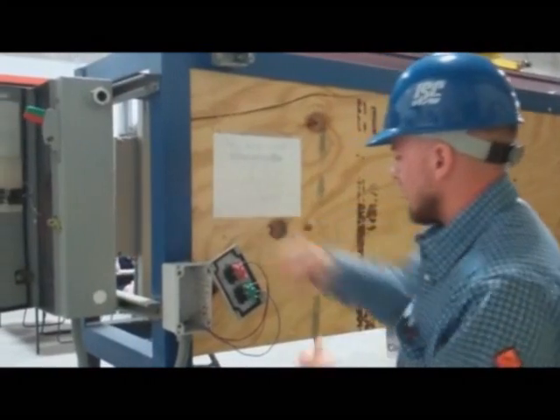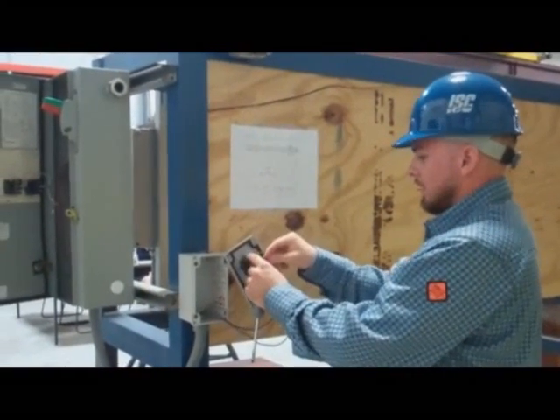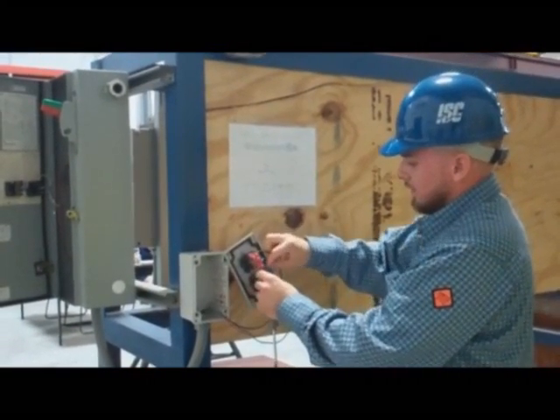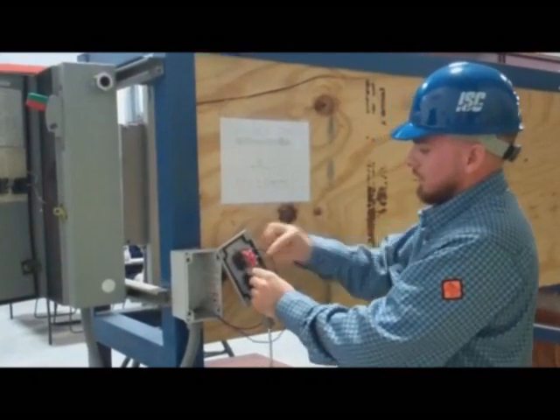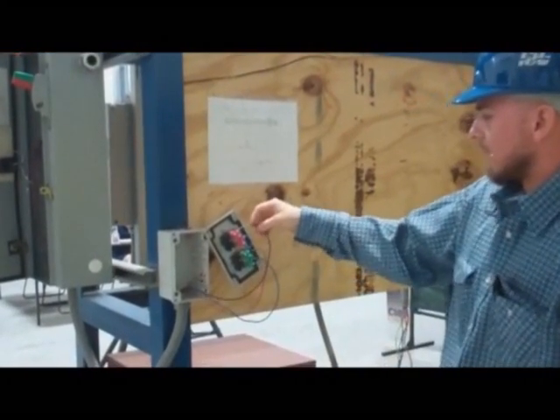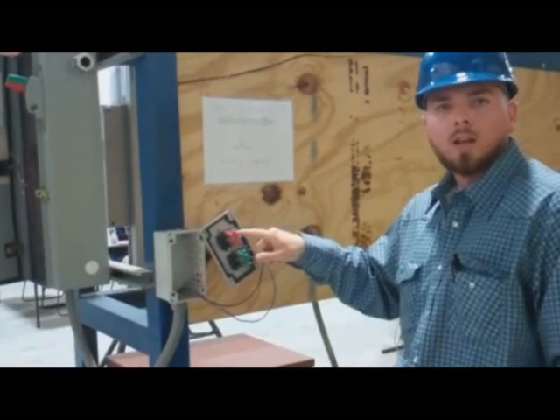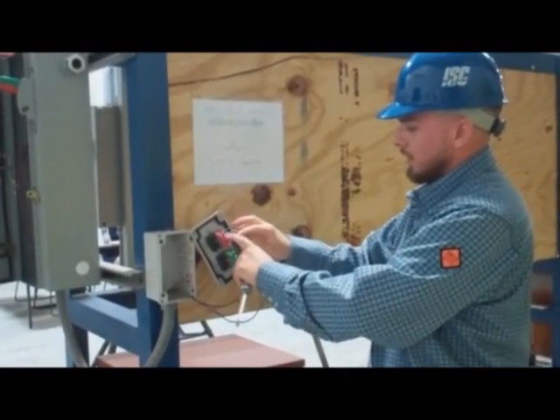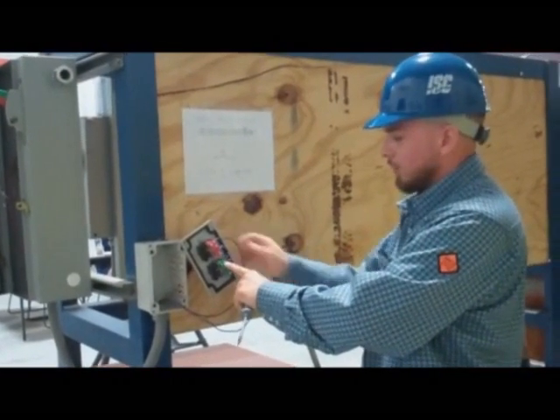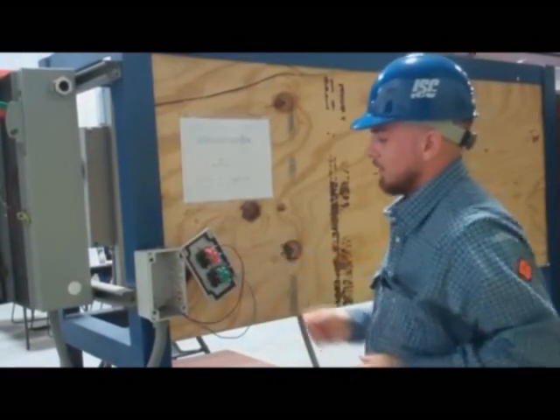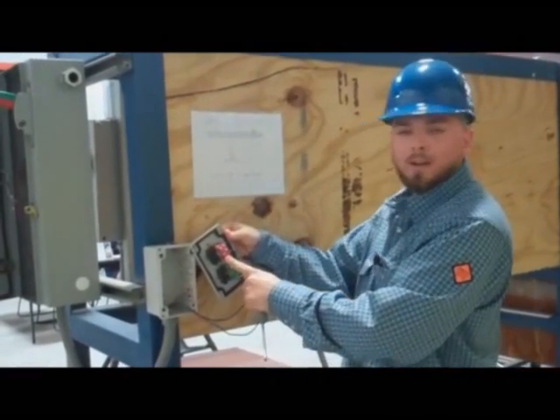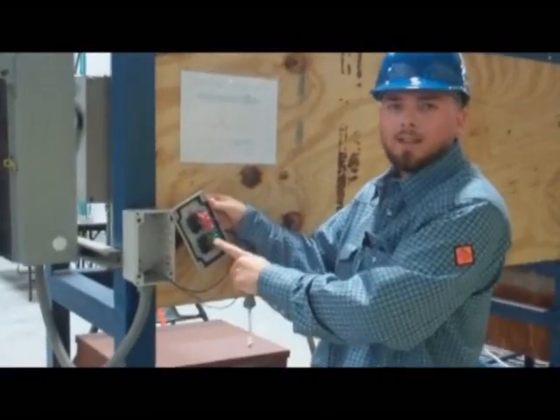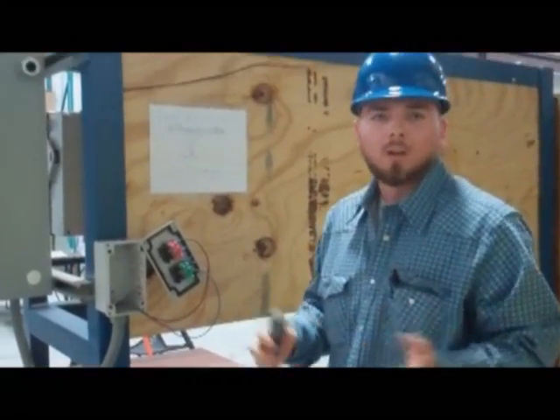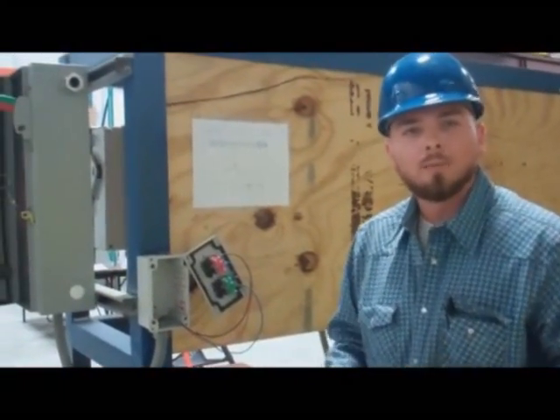And then you guys follow a jumper. What you have is you have your black wire coming out on your normally closed on the stop. It jumps over, because these normally closed contacts, it jumps to your normally open on your start. So when they stop that motor, you push that stop button, it opens up those contacts, and that kills the power to the motor. So they can stop and start whatever they need to get the process going through the pipes or whatever they're doing.